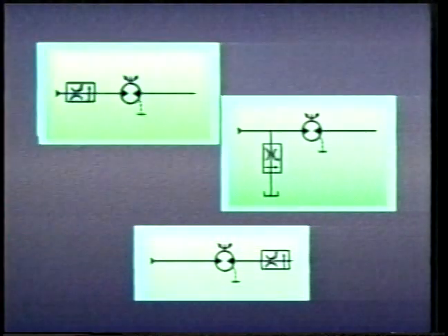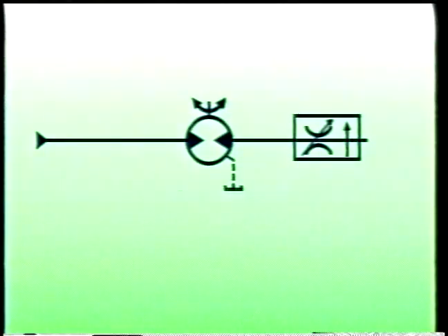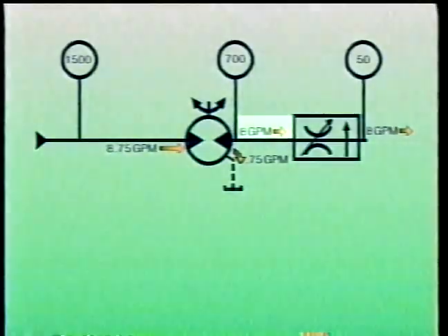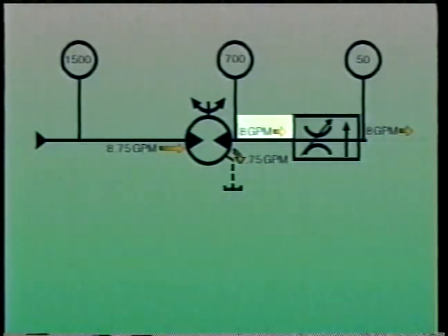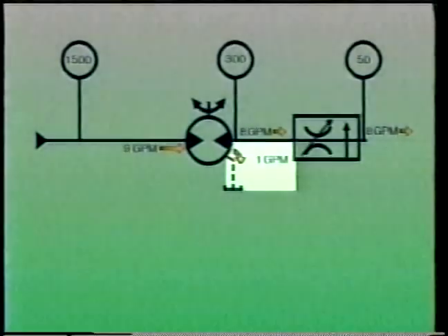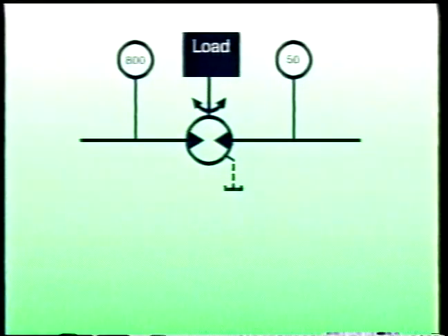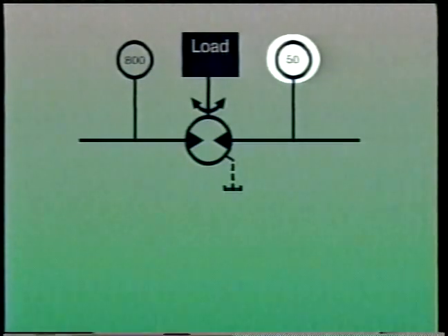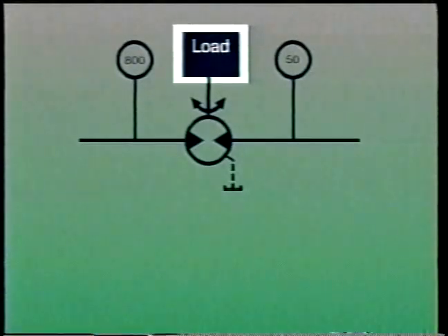However, flow control valves in meter out circuits control the flow that actually goes through the motor. Installing the valve just downstream of the motor will control the motor speed regardless of variations in pressure or leakage. We learned earlier that changes in inlet pressure can affect the torque a motor produces. Torque can also be affected by changes in outlet pressure and by changes in load.